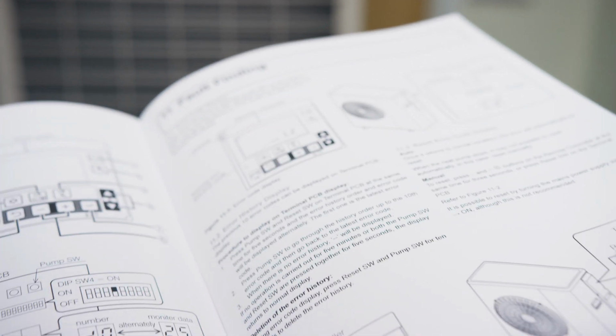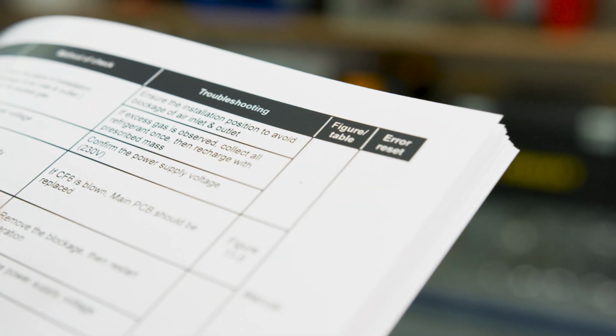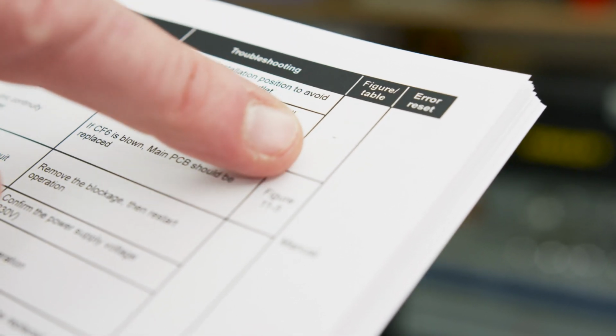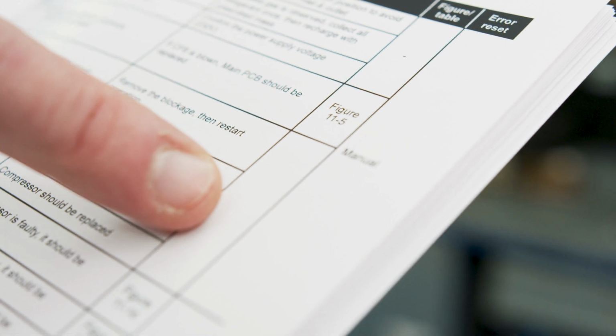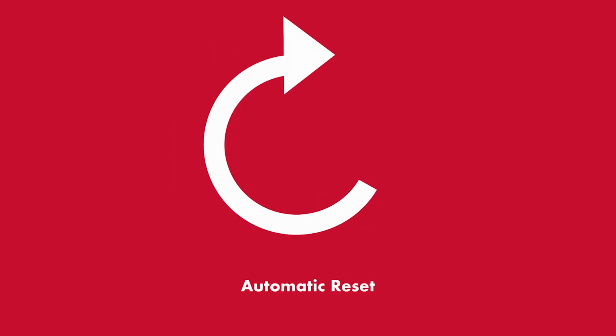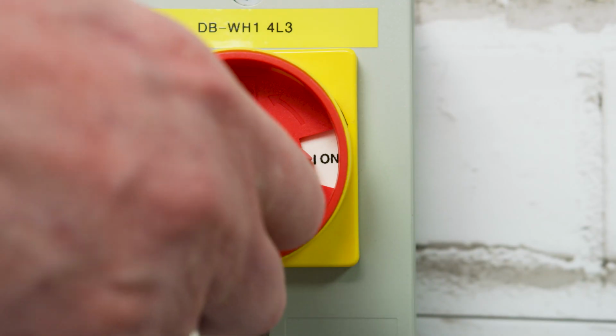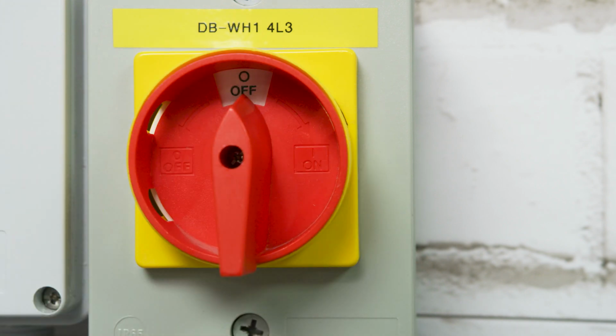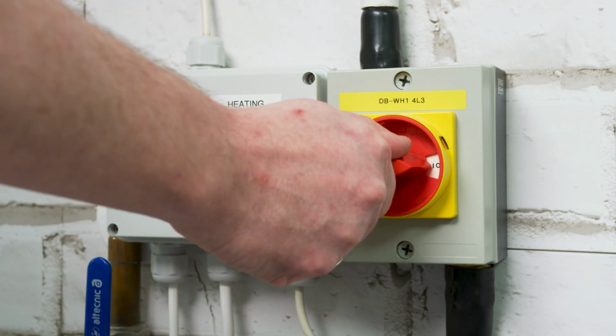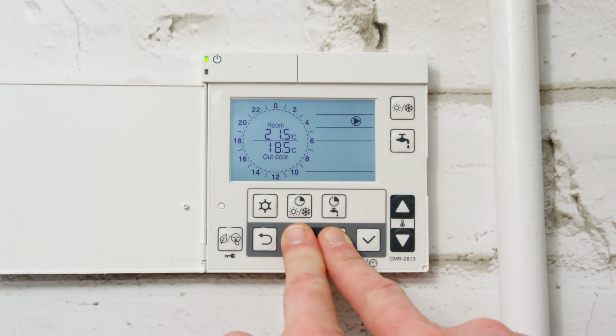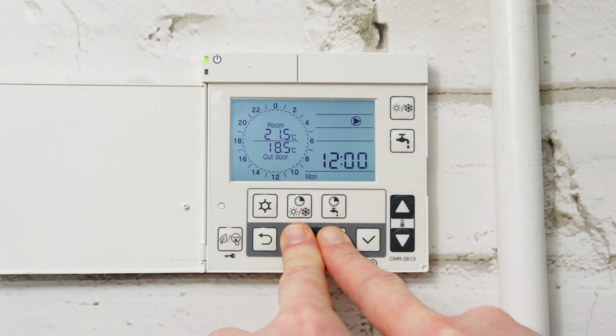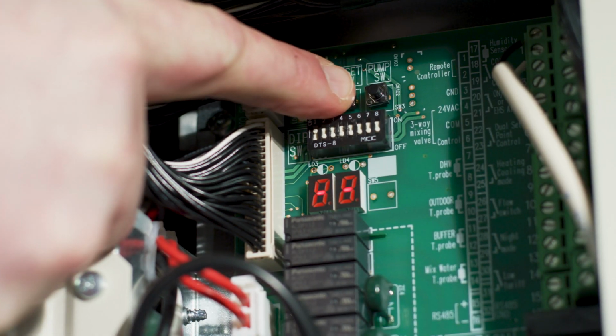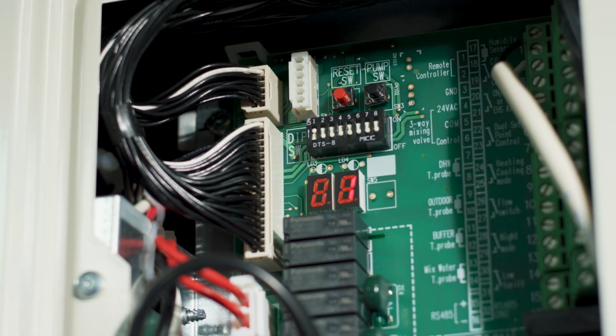Once the fault has been rectified, the error code must be reset. This can be done in one of three ways, depending on the error code concerned. Method one, by automatic reset. This happens when the heat pump returns to normal operation. Method two, power off, by turning the electrical supply to the heat pump off and back on again at the external isolator. Or method three, manual reset, by either pressing the plus and minus on the controller or pressing the reset SW switch, red button, on the terminal PCB.